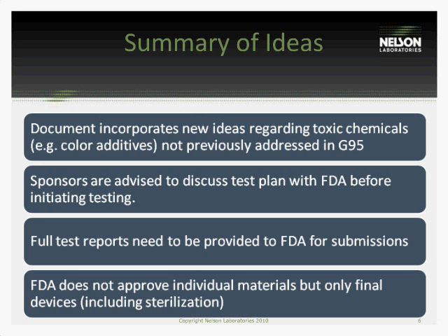The next one is sponsors are advised to discuss the test plan with the FDA before initiating testing. And this is something that we've stressed for a very long time here at Nelson Labs. These biocompatibility tests are so long and so expensive that it's nice to go into the testing with confidence that as long as the testing is performed correctly and the results are good, you're doing the correct test plan. So this is a way to get feedback from the FDA on specific tests, and you have limited opportunity for surprises when you actually submit those tests at the back end.